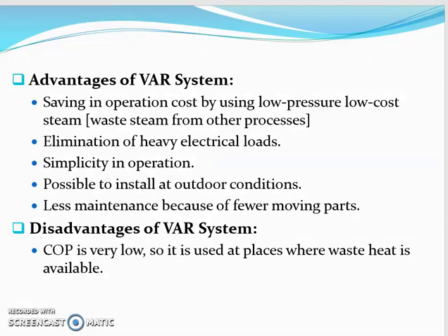It eliminates heavy electrical loads. The electrical load requirement is only at the pump, and its operation is simpler, and it can be installed in outdoor conditions as well. It requires less maintenance because the pump is the only moving part. Disadvantages: its COP, coefficient of performance, is low, so it is used at places where waste heat is available.